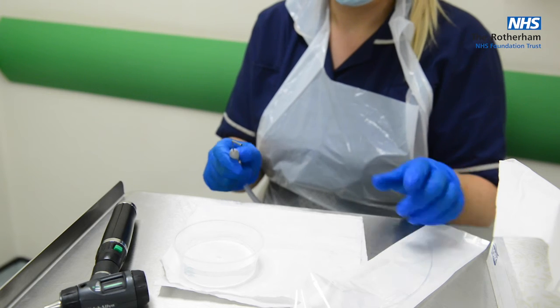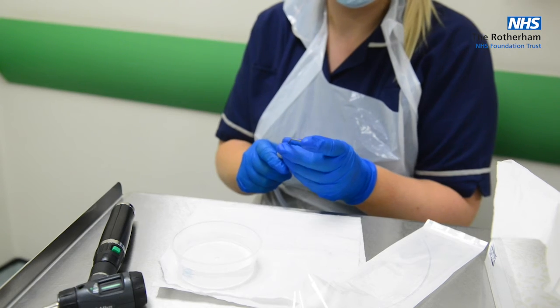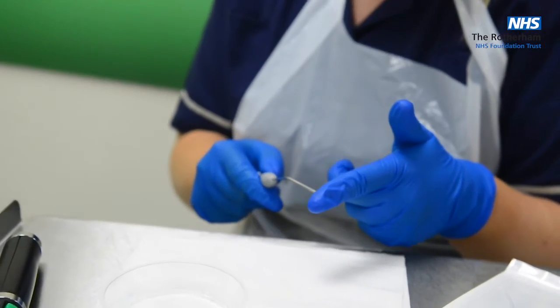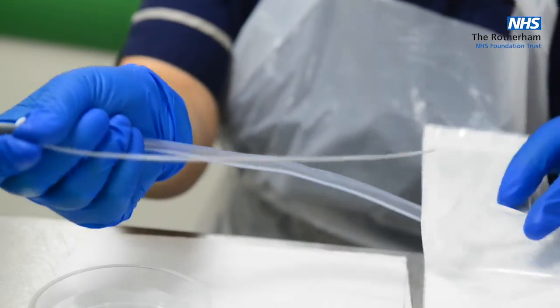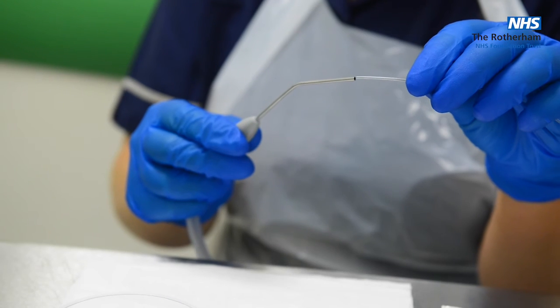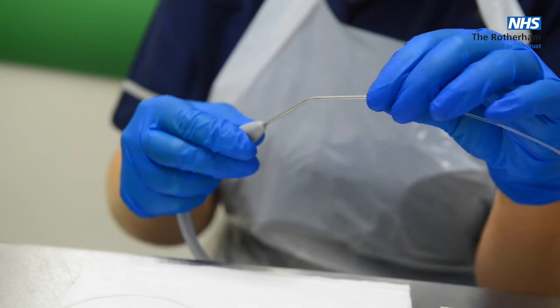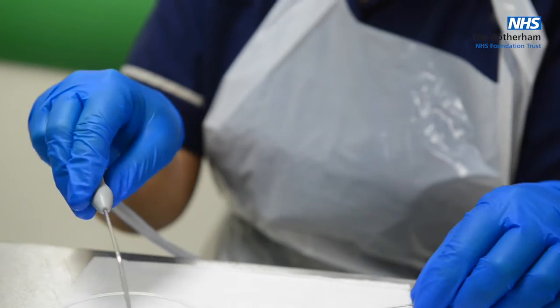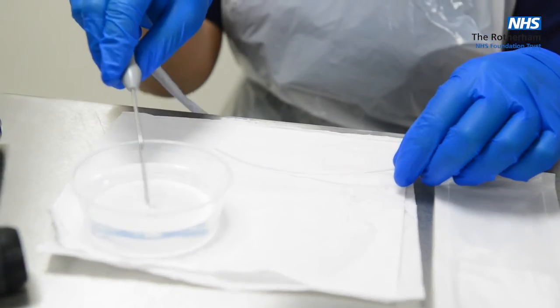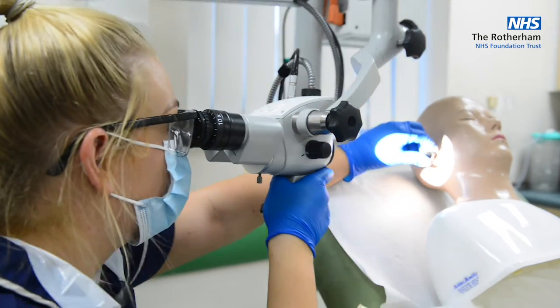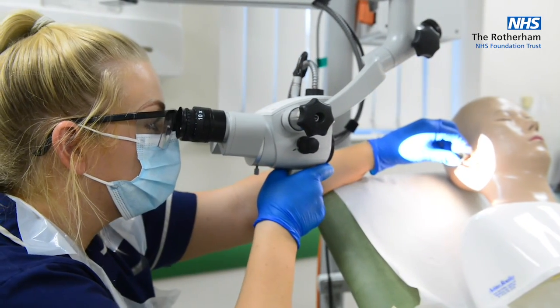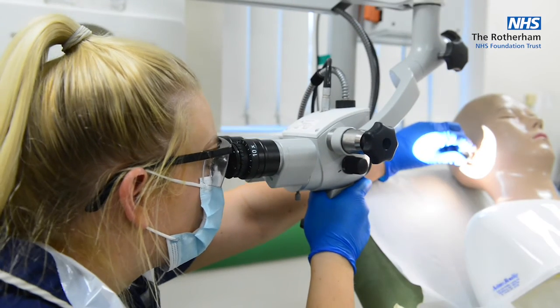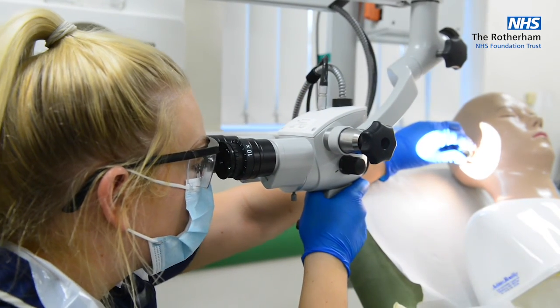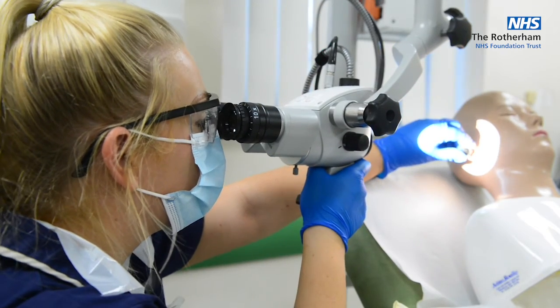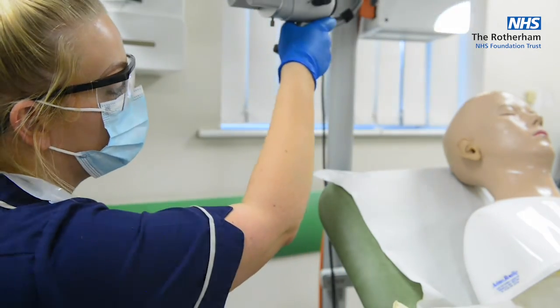Really soft wax debris can cause the Zollner suction tube to become blocked. This can be cleaned using a cleaning pipe provided in each single-use pack, or rinsed through with warm tap water from the gallipot. Reposition the microscope to various different angles to inspect all of the meatus once all of the wax or debris is removed. The ear should be examined again following otoscopy guidelines.